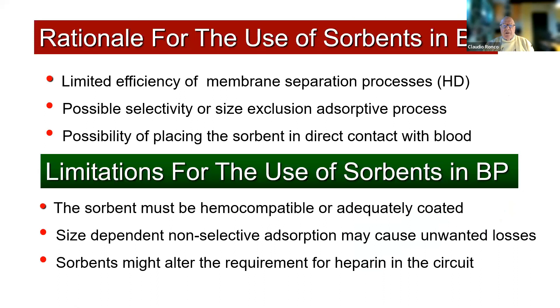The rationale for the use of sorbents is the limited efficiency of membrane separation processes, the possibility to selectively remove some solutes, and the possibility to place the sorbent in direct contact with blood. There are also limitations: the sorbent must be hemocompatible or coated, size-dependent non-selective adsorption may cause unwanted losses — for example, antibiotics can be removed — and sorbents may alter the requirement for heparin in the circuit.